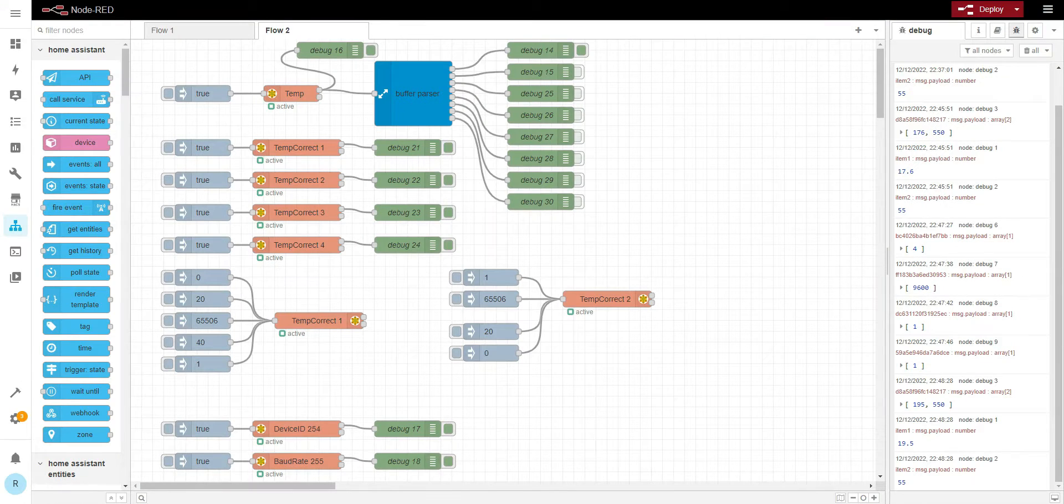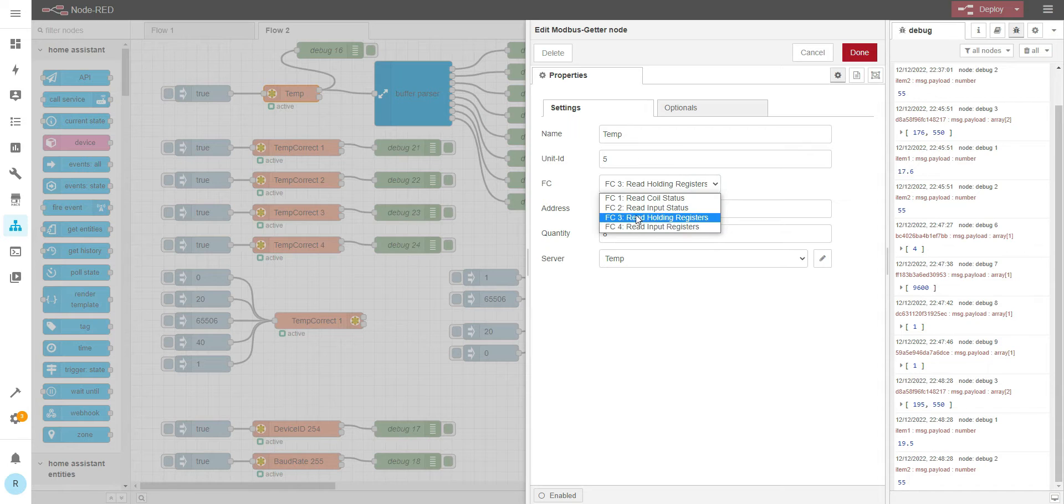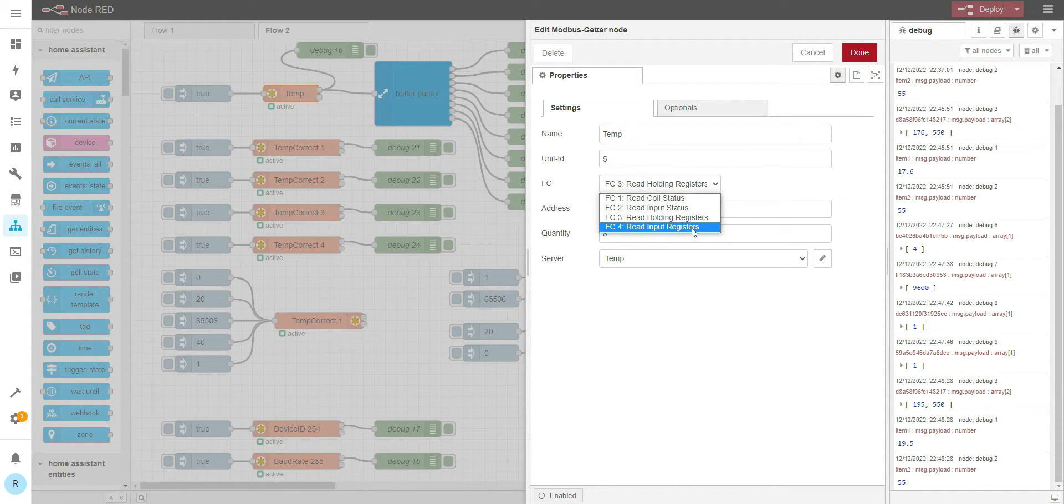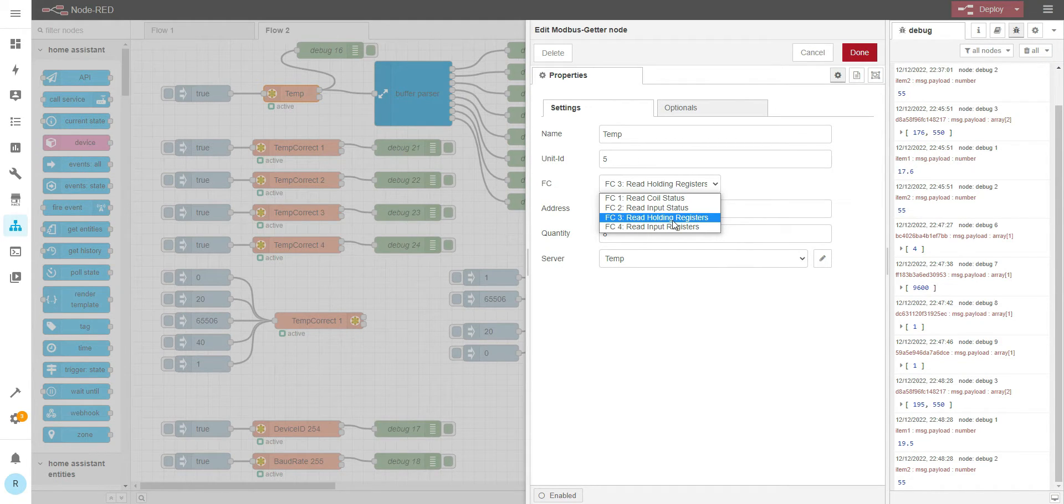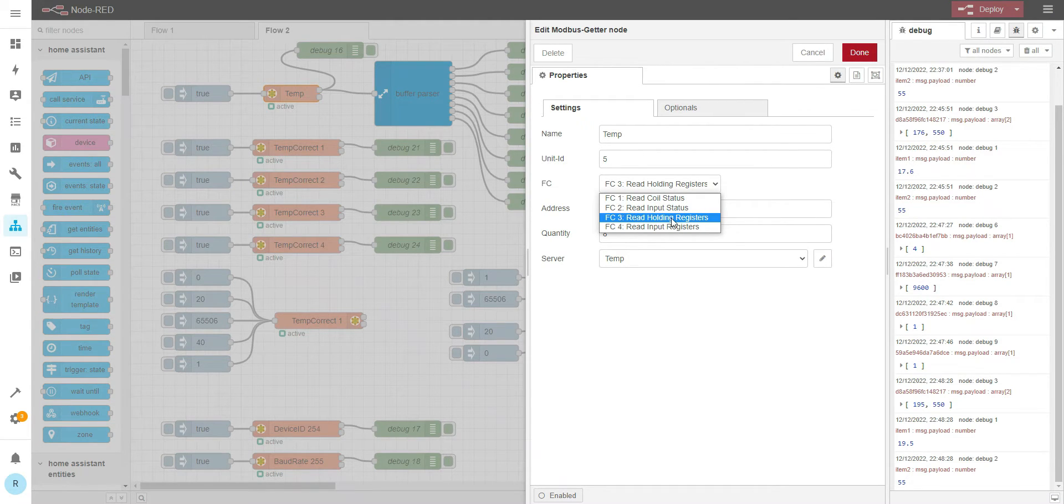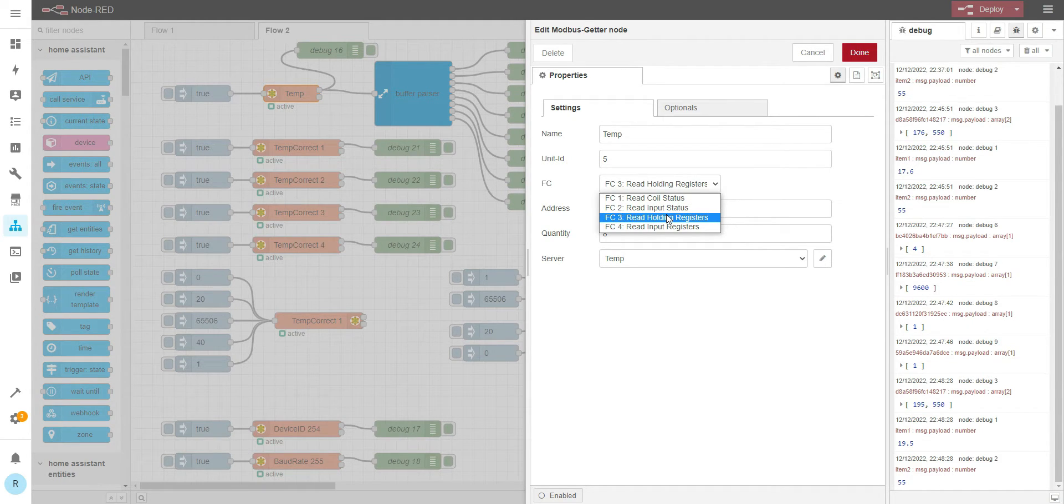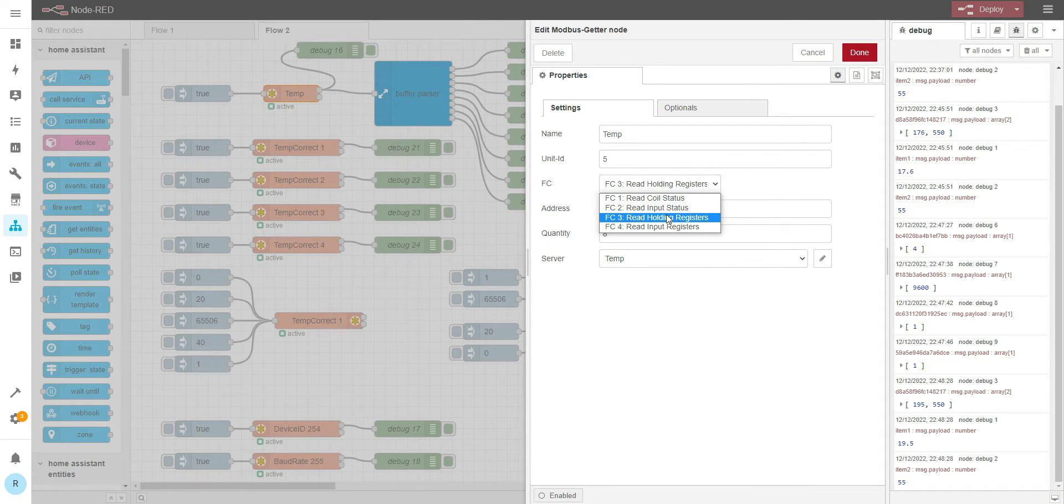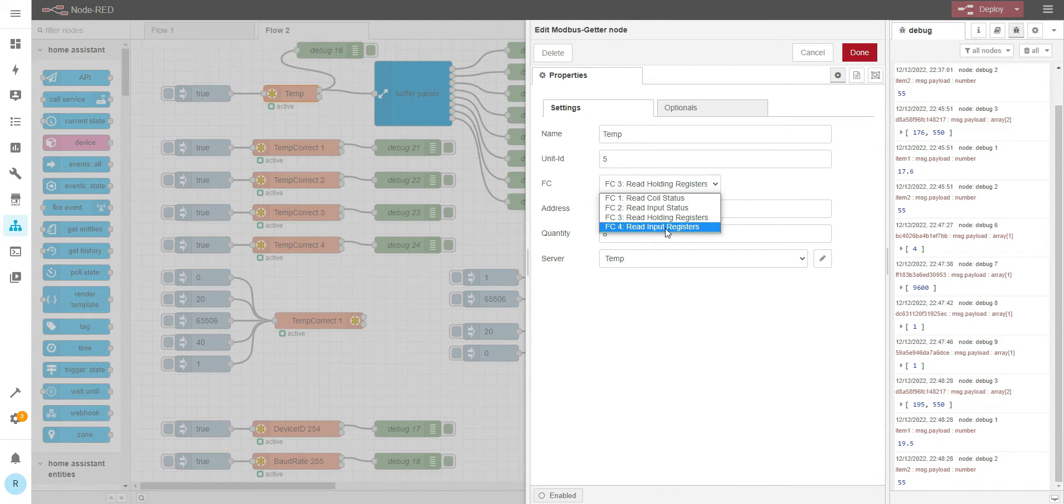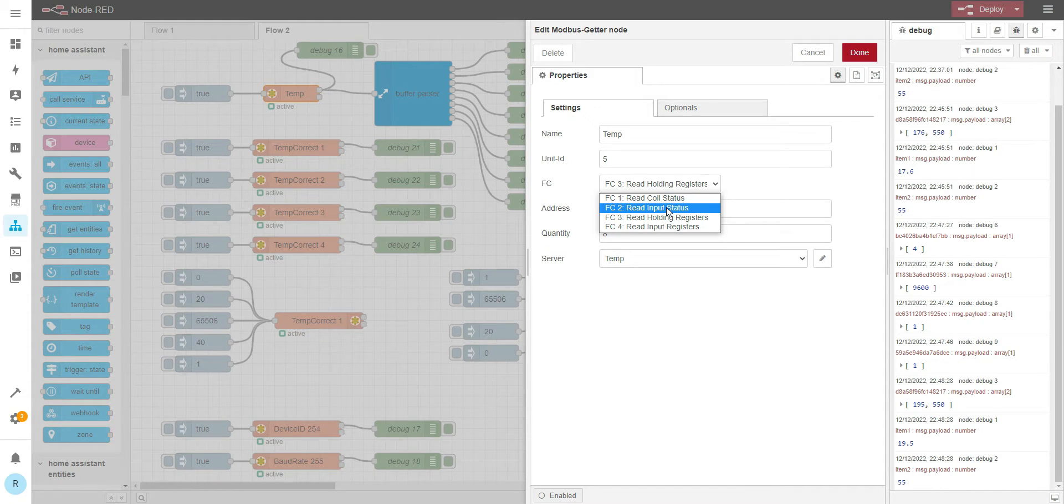To read, we're using function code 3. Instead of reading input registers like the previous unit, we're reading holding registers. What's the difference between holding register and input register? It's exactly the same difference as coil or input status. You can read it and write to it, means preset the register. Same like coil, you can read the coil and force the coil. Input register is just read value, same like input status.